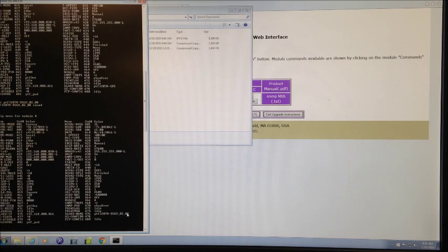So now we've set the instrument up, it knows where to go to get the file and what the name of the file is. The next thing that we're going to do is disable the watchdog in the instrument. There is a hardware watchdog in the instrument, and if the instrument doesn't tweak that every few seconds, then it will reboot the instrument. However, while we're upgrading the software, we actually disable all the tasks that would normally tweak that watchdog, so we do not want the watchdog resetting the instrument. So for the purposes of upgrading, we will disable the watchdog.